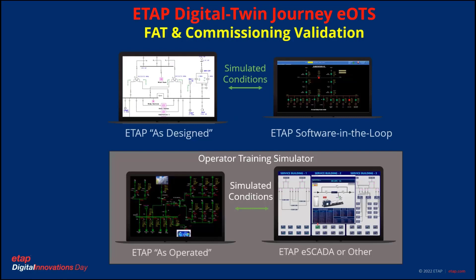So with that, the digital twin journey: once you have done the overall electrical designing, you have an as-designed model, and you take that model and run all the simulated conditions, bringing in the software-in-the-loop model, which converges into an ETAP OTS environment. It integrates with the existing SCADA, or a new SCADA from ETAP or any other OEM, and creates the operator training environment. When it goes to an operational environment, you have the operating stage feeding into SCADA, you get conditions and create as-operated, and ETAP brings as-operated to as-validated. You validate the system before operations, and then eventually deploy the control as required into the field.